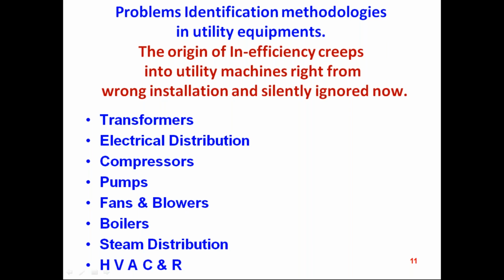This is where we are concentrating. When you go as an energy auditor to the industry, the aspects we see are whether the machines are loaded correctly, whether they are underloaded, overloaded, or optimally loaded. For a given transformer, the transformers we have in the industry are all 10 or 20 years old, which are not capable of handling the K rating, or you can say the nonlinear loads from the demanded process.